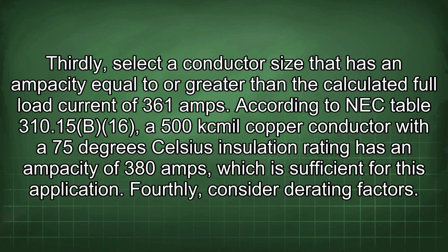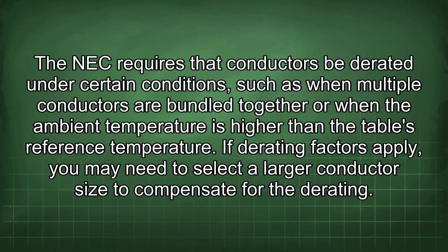Thirdly, select a conductor size that has an ampacity equal to or greater than the calculated full load current of 361 amps. According to NEC table 310.15(B)(16), a 500 kcmil copper conductor with a 75 degrees Celsius insulation rating has an ampacity of 380 amps, which is sufficient for this application. Fourthly, consider derating factors. The NEC requires that conductors be derated under certain conditions, such as when multiple conductors are bundled together or when the ambient temperature is higher than the table's reference temperature.